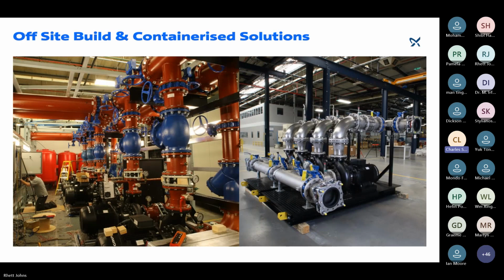And this would mean that when it's installed, it's going to come pre-tested, it's going to come commissioning ready, in what we would call a turnkey solution. And it has a real advantage for a contractor or an EPC, because from their perspective, this is going to dramatically reduce their workload from a design, procurement and an installation perspective, because obviously this has all been consolidated under one supplier. So you don't have any surprises, so to speak, on site if something can be supplied as one complete unit.